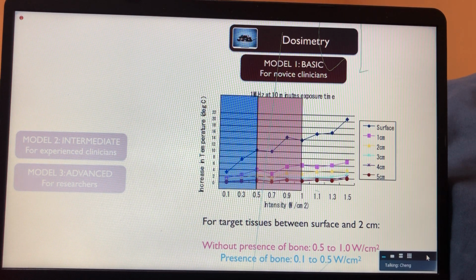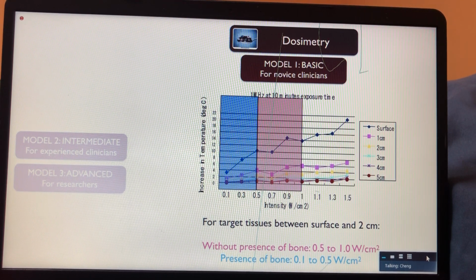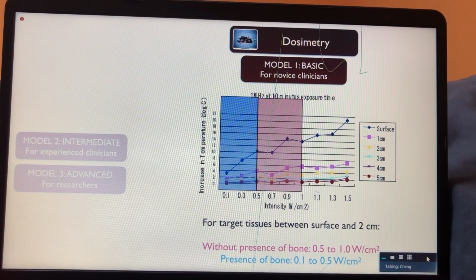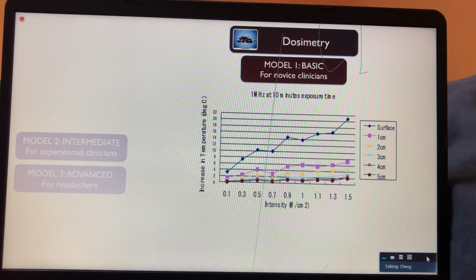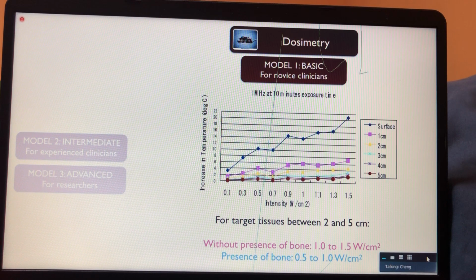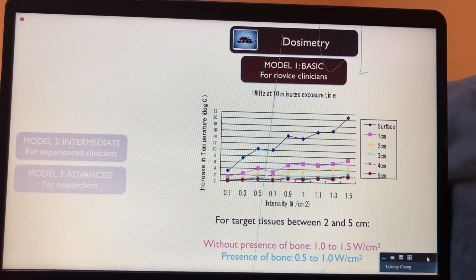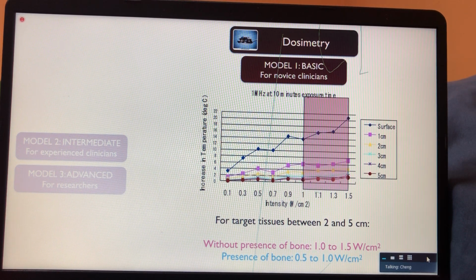But now we are saying even the presence of bone, don't worry about it. So even less, you only need to worry about the brown box there. So between surface and 2 cm is 0.5 to 1 watts per cm squared. That's probably what we were all doing before, because I was always going at either 0.5 or 1 watts per cm squared when I was doing my treatment. And it was always 10 minutes. I didn't realize it at that time, but that's what I was doing. So it didn't matter. It was in that range. For things that are between 2 and 5 cm, then it was 1.0 to 1.5 watts. That brought it into the Goldilocks zone there.